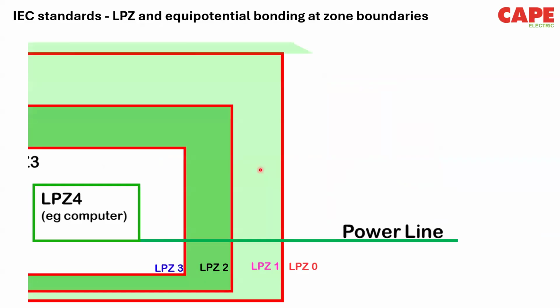So in lightning protection, we have something called zones of protection. Zones of protection means at zone 0 there is a direct lightning strike, and inside zone 1 there is no direct lightning strike, but maybe the indirect effects of lightning can be felt. Zone 2 is where the effects are a little bit reduced compared to zone 1, and zone 3 is where the effects are furthermore reduced. So whenever we design a lightning protection system, we have to define the zones, and depending on the equipment which is used, we have to categorize them whether they are safe to be used in zone 1, zone 2, or zone 3. So there is a wonderful presentation which has been done on YouTube. You can find that.